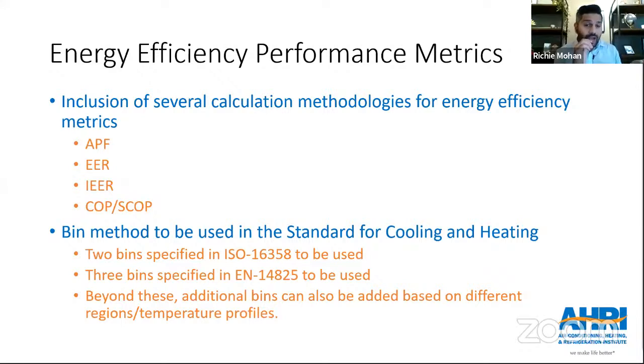There are several bins which have been extracted, or rather copied, from various regional standards as well as ISO standards, and they're going to be added as part of an addendum in the global VRF standard, such that the user of the standard can then use a bin set which is most appropriate to the user's region. At the moment, we've got 2 bins which have been taken from the ISO 16358 standard, and this is for cooling. And then we've got 3 bins which are in EN 14825, and this is for heating, which have been added into the addendum. But this is not the complete set. We understand that there will be additional bins which we will need to add based on the requests coming in from different regions with their different temperature profiles.